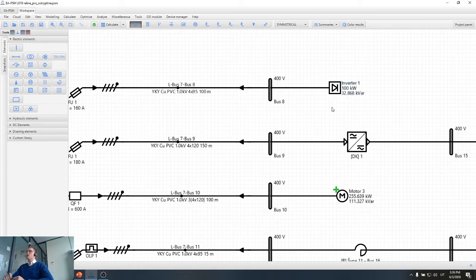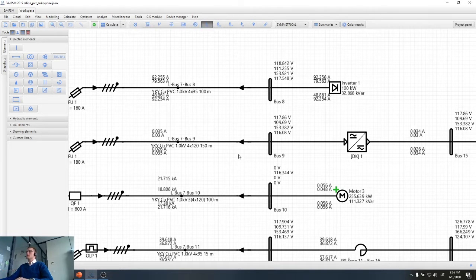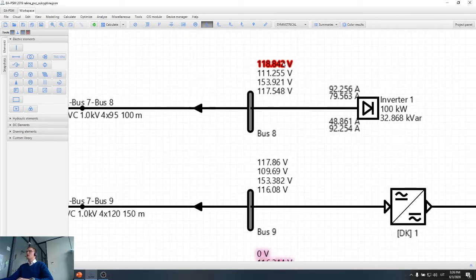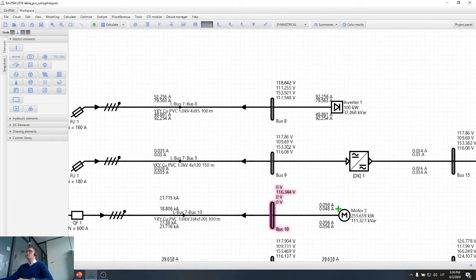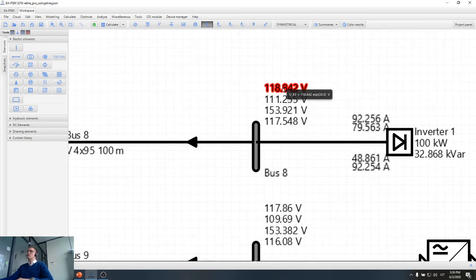So usually we don't have to set any settings for the inverter protection, except maybe for solar inverters, where we can also provide disconnection times. But normal inverters like variable frequency drives already have under voltage protection devices. If we have a short circuit somewhere in the network, let's say we calculate a short circuit in bus 10, we will see that we have lower voltage than normally.